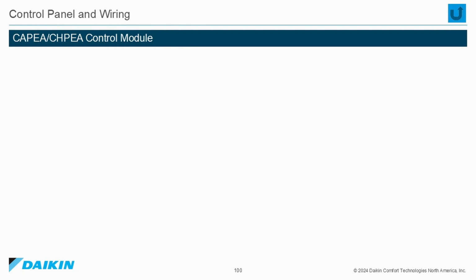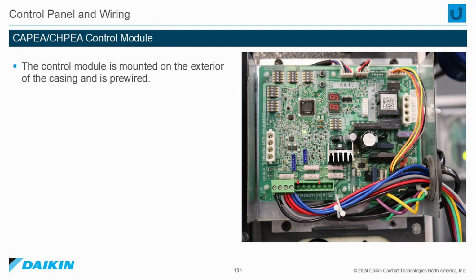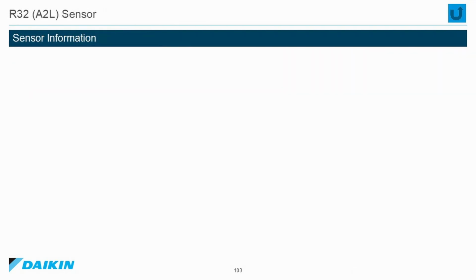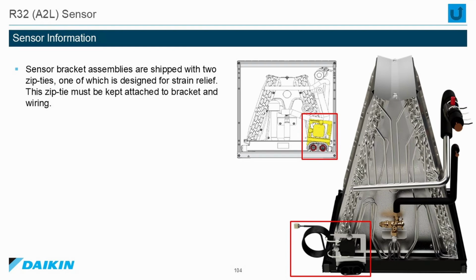CAPEA and CHPEA control module. The control module is mounted on the exterior of the casing and is pre-wired. Verify plugs and wires are secure on the board before powering the system. Sensor information. The sensor bracket assemblies are shipped with 2 zip ties, one of which is designed for strain relief. This zip tie must be kept attached to the bracket and wiring.